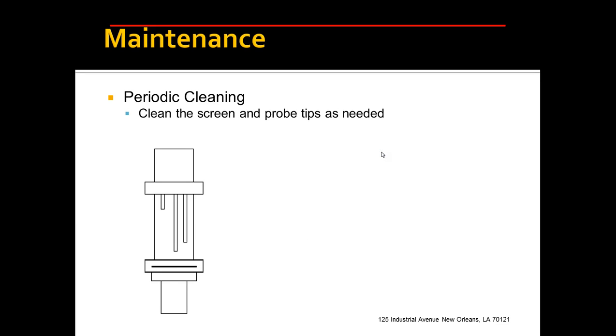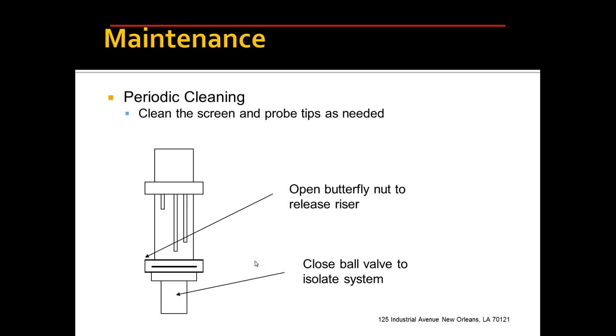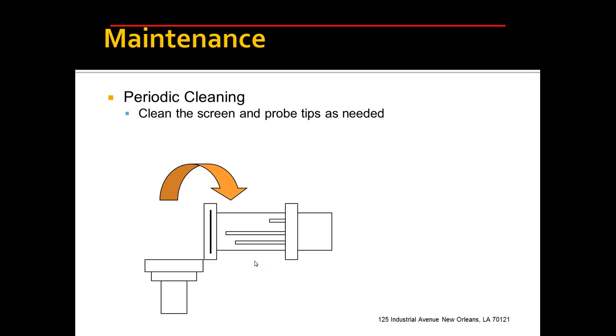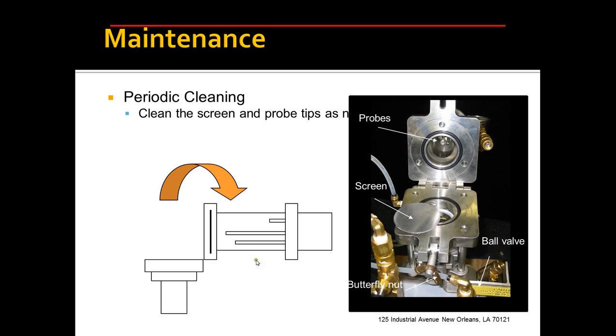Let's take a look at what periodic cleaning looks like. As I said, you clean the screen and the probe tips as needed. There is actually a ball valve, as I mentioned, to isolate the system. When you close the ball valve, it exposes a wing nut, which you can then open up to release the riser, and the riser will basically just swing open and give you access to all the things that need to be cleaned. Here's a picture of what it looks like.